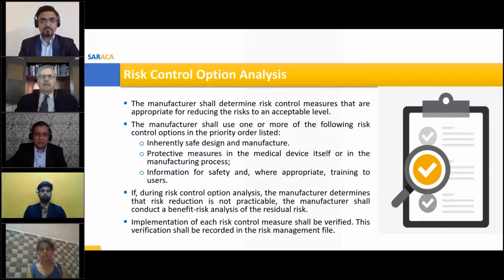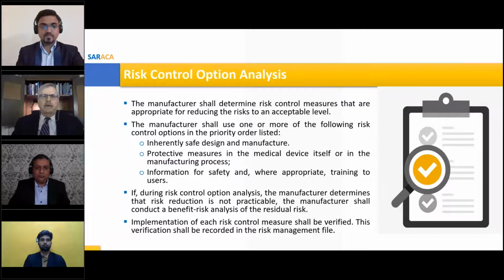Protection measures in the medical device itself or in the manufacturing process refers to this. It would be, for example, removing rough corners on a device so that you don't induce a cut or a laceration when you're moving the device from one location to another. If it's too heavy and you try to move it, should you be including wheels? Should you be including a cart for that? And then the last but not least is what kind of information will you include to ensure the safety and where appropriate training for use of the devices.